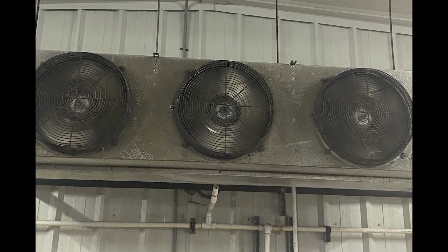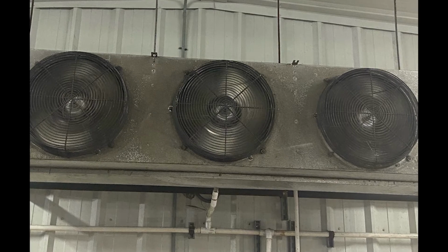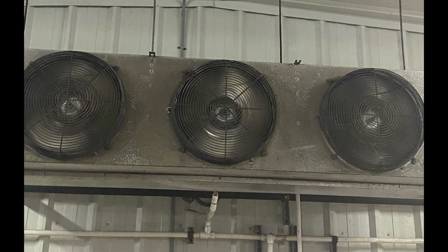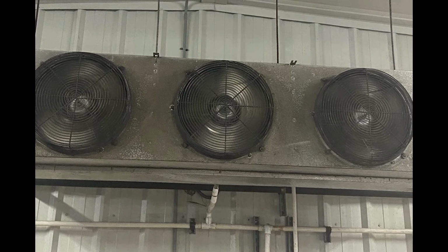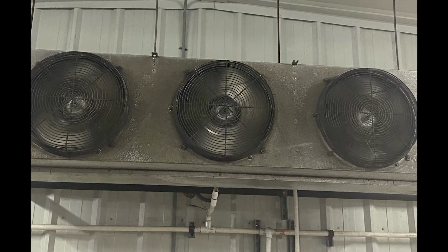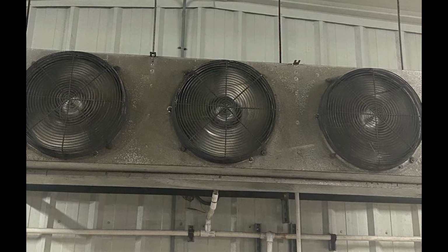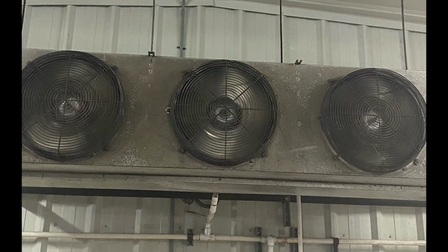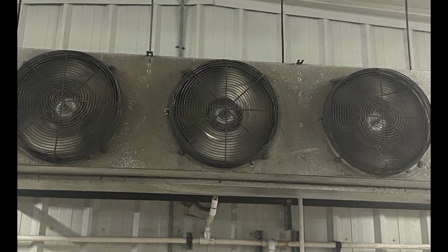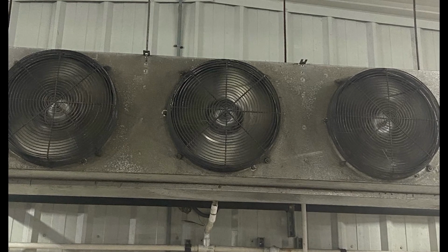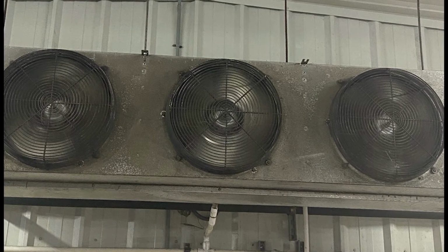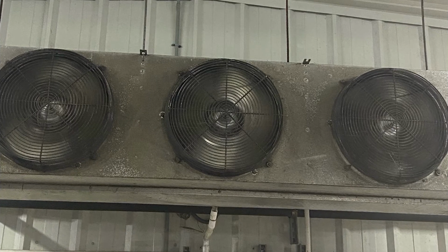The condensers and cooling units must also be clean. Dust is a common concern, and the cool, damp environment of the cooler can lead to mold and mildew growth. Attention should be paid to the external casing, as well as grates or grids, drip lines, and any mounting hardware. If these components cannot easily be observed from the floor, the AMS supervisor should work with management to develop an acceptable alternative method of assessment.